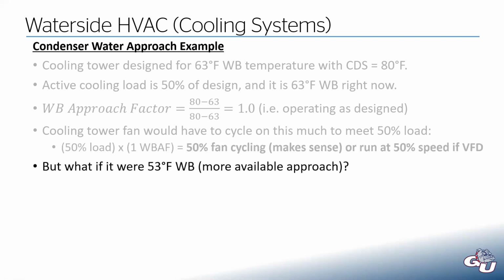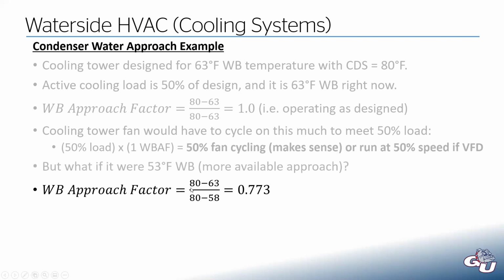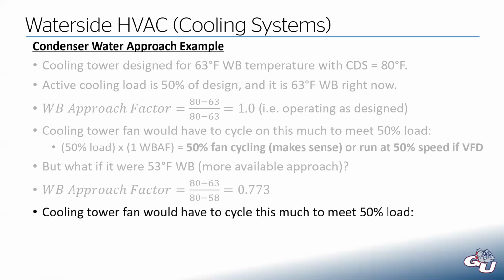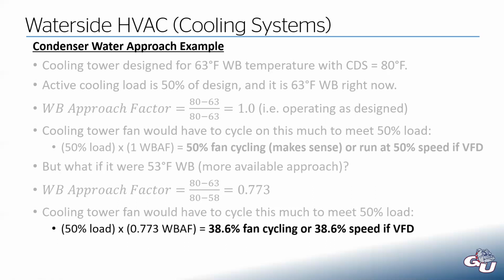But what if the next day it was at 53-degree wet bulb, which means we have more available approach? Our new approach factor would be our design delta, 80-degree supply minus 63-degree wet bulb, divided by what our available approach is today, 80 minus 58, and we come up with this factor of 0.773. So what would our fan cycling be now? 50% load times that 0.773 approach factor. So now it only needs to cycle on about 39% of the time. And so you can see how if we have more available approach, that's going to lead to less cycling of the fan or a lower fan speed, and vice versa.